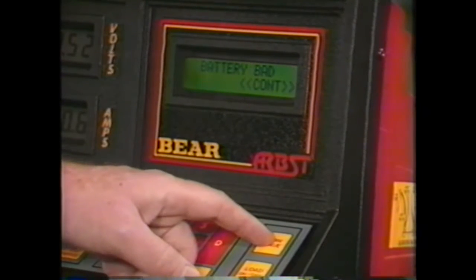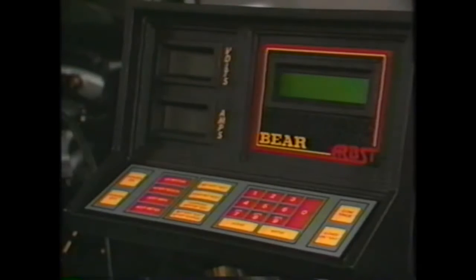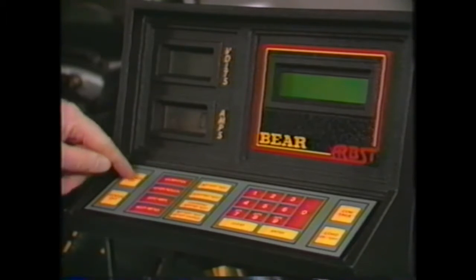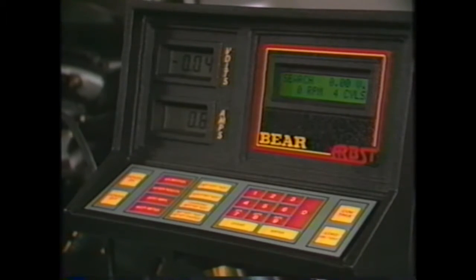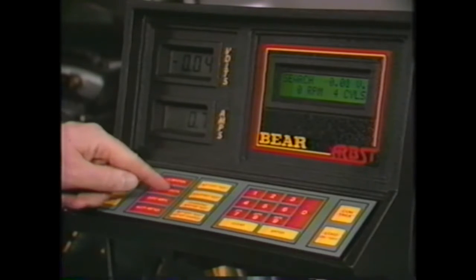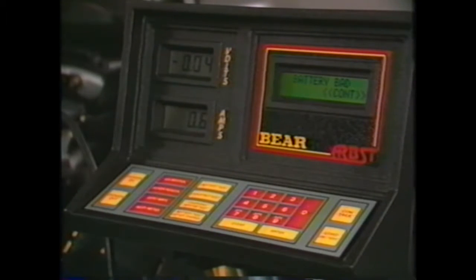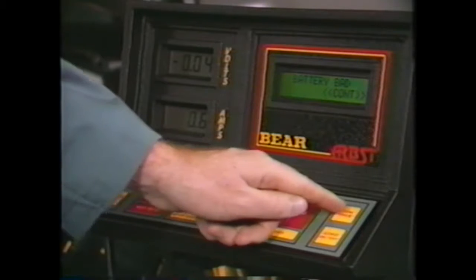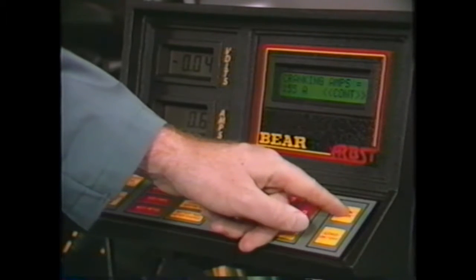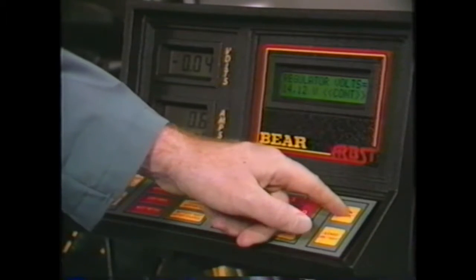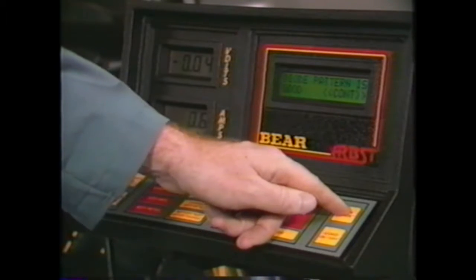Test results are always saved in this manner. The results are even saved after the tester power is shut off. To retrieve results after the power has been shut off, turn power back on. Then press the Review Results key. When you press any other test key after turning power back on, all the old results are cleared from memory to make way for a new testing session.